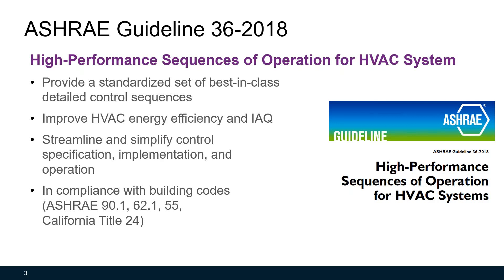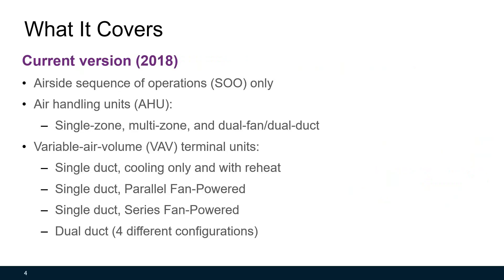The guideline is in compliance with building codes such as ASHRAE 90.1, 62.1, 55, and California Title 24. The current 2018 version only contains air-side sequences — no water-side sequences like chilled water plant control. It only applies to forced-air variable air volume (VAV) air handling units and VAV terminal units. There is no rooftop unit control, chilled beam systems, variable refrigerant flow (VRF), or dedicated outside air system (DOAS) controls.